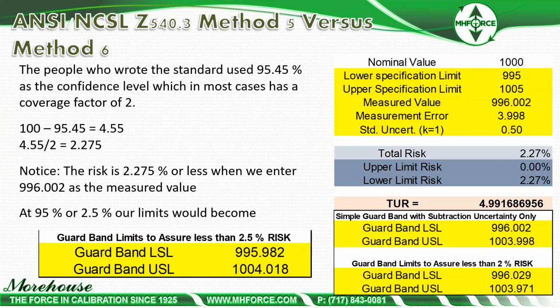And here we're getting into more about the standard and what's going on. The people that wrote the standard use 95.45%, so that's a coverage factor of 2. You can see on this slide that the risk is 2.275% or less. So really what this whole slide is, is guard bands to assure less than that risk. So this says I have a device that's plus or minus 10 pounds. What happens when I actually apply my guard band and look at it here?